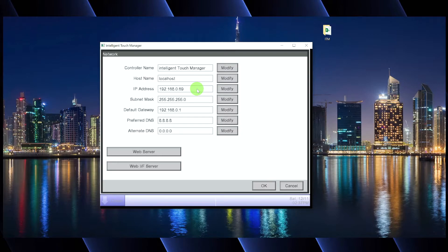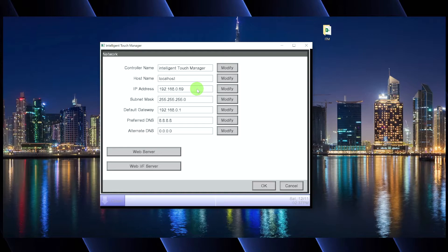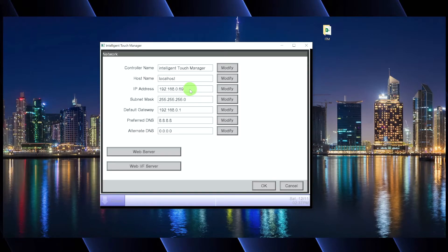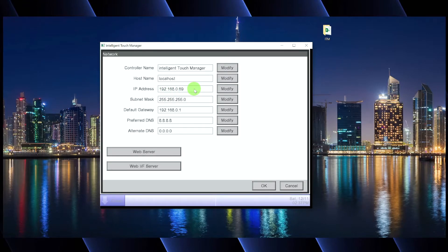Now, this is really important when it comes to remote access, things like DNet monitoring, which is something that Daikin will use to actually monitor all the equipment 24-7, 365. They need access to this ITM for the software. This IP address needs to be a static IP address.